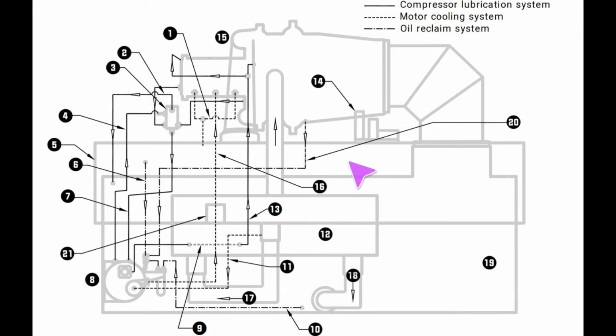Continuation of that, all of that conversation leads us to this point. So this may look very intimidating, and that's okay. So let's break it down as best we can. So before we get into any of the rest of this, let's just first get our bearings as to what it is we're looking at. So this bottom piece of the machine here, this is your evaporator, right? You can tell this is the compressor. This particular one we're looking at, we see there's one pipe coming off the economizer. Here's the motor. We count 1, 2 ridges. Okay, so all of these are identifying this is a 2-stage machine, being a CVHF series.